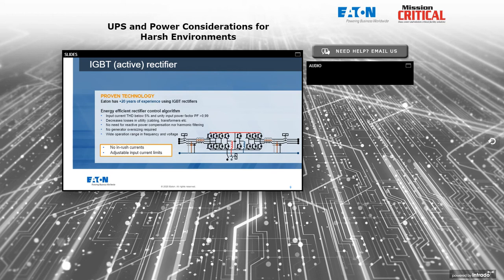But dramatic generator oversizing should not be required if the UPS utilizes an active rectifier. It also allows a wide operation range. It'll accept input frequency from, say, 40 hertz to 70 hertz, and a voltage from maybe as low as minus 25% of nominal to as much as 20% of nominal on the high end, plus minus 25 to plus 20%.